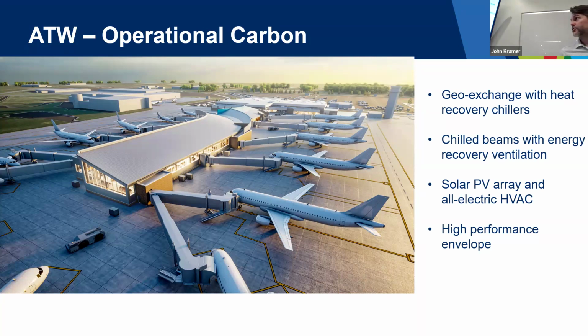And then chilled beams with energy recovery ventilation, those are not super common. There are some, I've seen one up in Broomfield. There's a school they renovated and it worked really well to put these big chilled beams on the ceiling. They're an efficient way of conditioning a space. It's a little different than what we're normally used to, but it's a high efficiency way of sucking up warm air naturally and letting cold air drop down to the ground. So you're saving a lot on fan energy. And coupling that with energy recovery ventilation brings the ventilation air, the fresh oxygen, to the space, while also extracting waste energy and using it to potentially preheat the outdoor airstream coming in. So it's another really great energy saving measure.